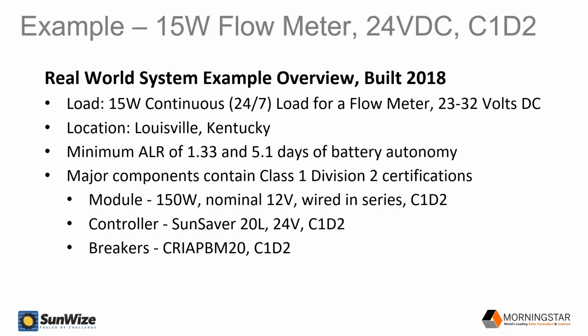The location was Louisville, Kentucky, and you'll see there are 2 key design parameters that I'm going to touch on: what we call an ALR, an array to load ratio, of 1.33, as well as 5.1 days of battery autonomy or battery backup. Then there are 3 major components within this system that contain Class 1 Division 2 certifications. That's the solar module, which we just discussed. In this case, we're using a 150 watt nominal 12 volt wired in series Class 1 Division 2 solar module. And we used the Sunsaver 20L 24 volt C1D2 controller and C1D2 certified breakers for the control panel.